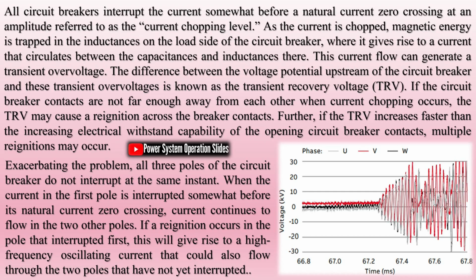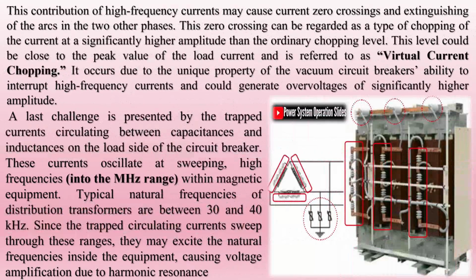The resistor, capacitor, and surge arrester together form a solution known as the RC snubber circuit, which has no known field failure cases, but its implementation results in an increase in transformer size and undesirable capacitor maintenance. Additionally, the installation cost of RC snubber circuits can go upwards of $20,000 USD and require system studies for sizing, which is often not a feasible option for organizations.